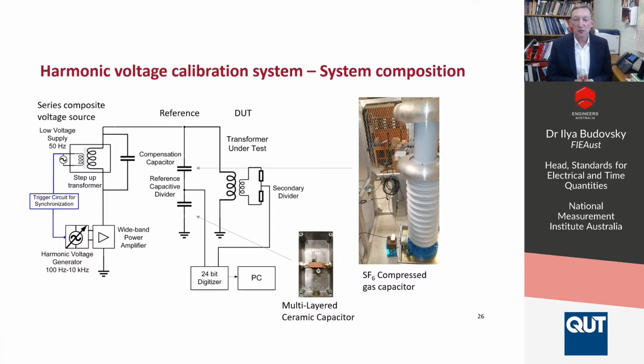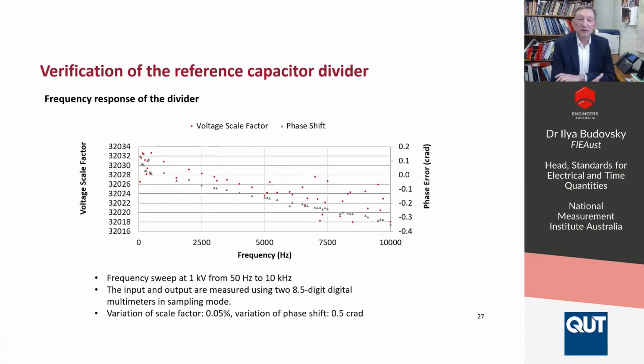Now, on the reference side, we have an SF6 compressed gas capacitor and a multi-layered ceramic capacitor forming a capacitive divider. And a 24-bit digitizer is measuring the output of the divider and the output of the transformer under test. So here's a frequency response, the first frequency response of the reference divider. You can see its voltage scale factor and the phase shift were measured up to 10 kilohertz, and we can see about 0.05% frequency response, but we can correct for that, and we are looking just where it comes from.